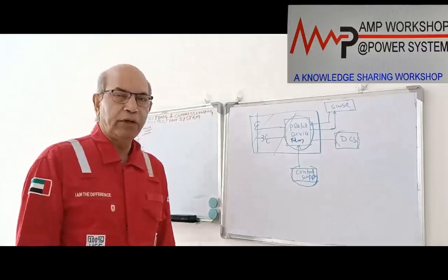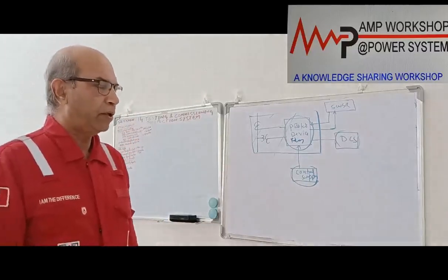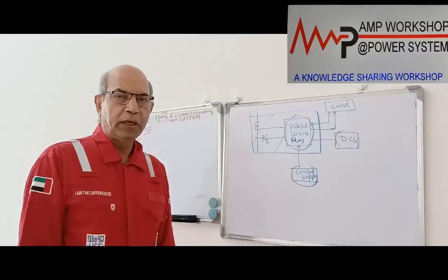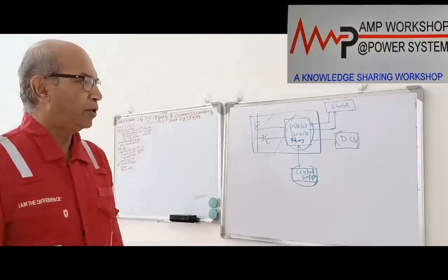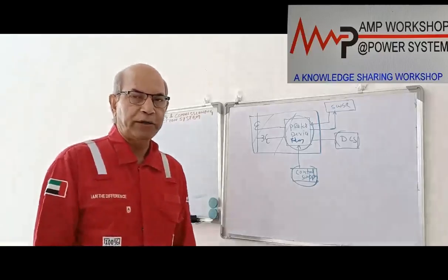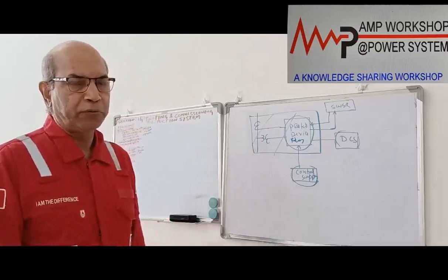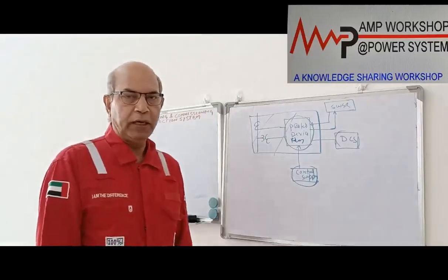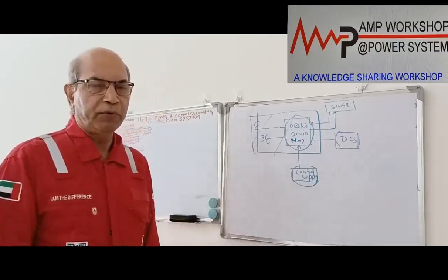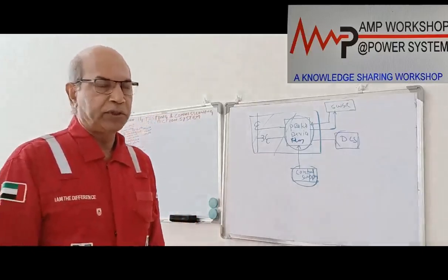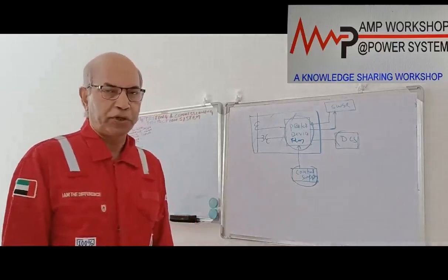Now, when we discuss the testing, commissioning, preventive maintenance, and troubleshooting of the protection system: in our session 1, we discussed that the protection system means the protection device, particularly the relay, together with its input-output devices. The relay alone cannot work. For proper functioning, it needs the input signal through the sensors, the CT and PT, which we generally consider an integral part of the protection system.